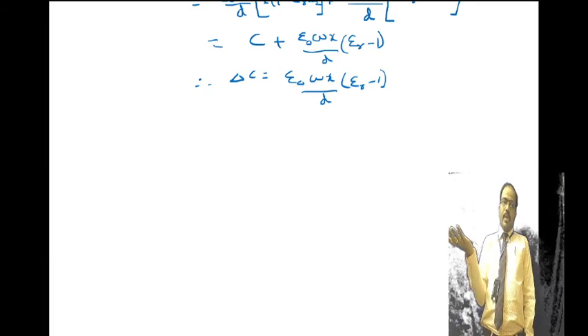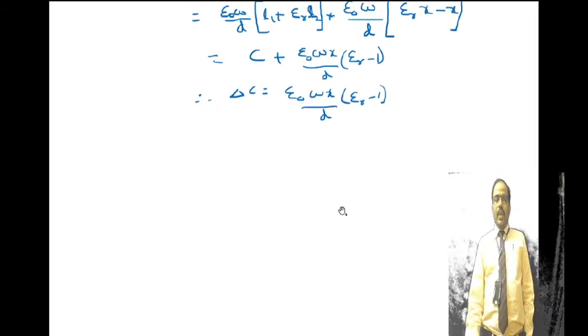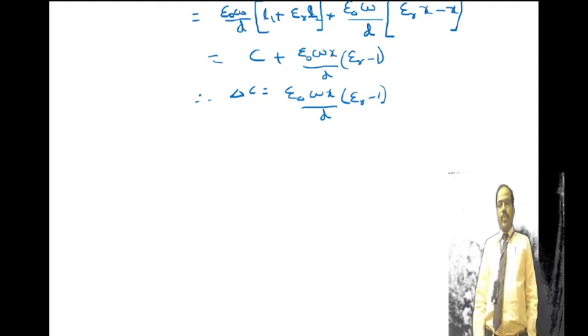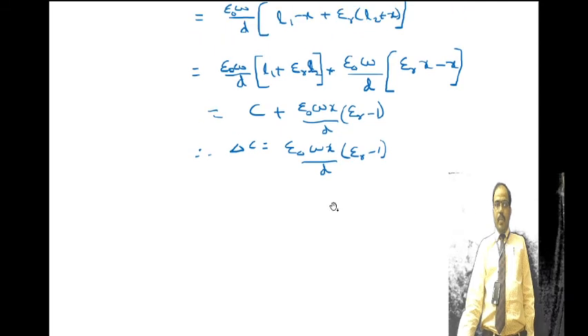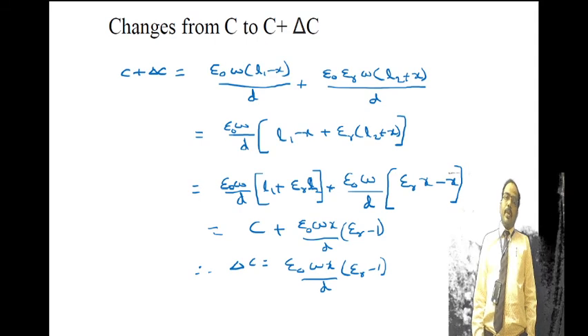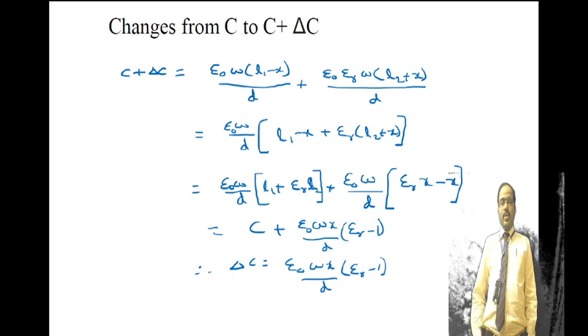We have discussed the measurement of displacement using capacitive transducers with three principles: change in overlapping area, change in distance, and change in dielectric medium. The same principles can be applied for measurement of force and pressure. The third principle — change in dielectric medium — can also be used for measurement of liquid level or gas levels in industrial applications. With this, the topic of capacitive transducers is complete.